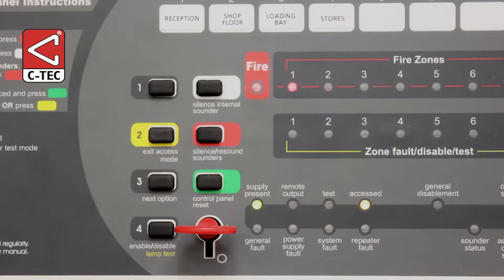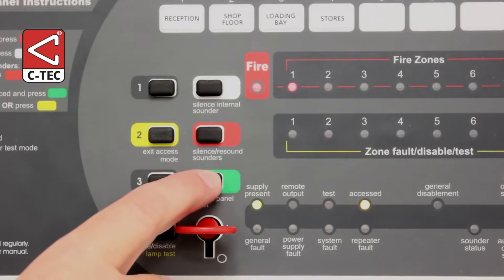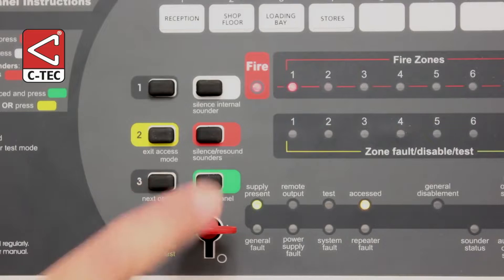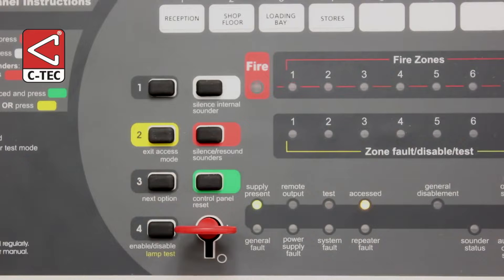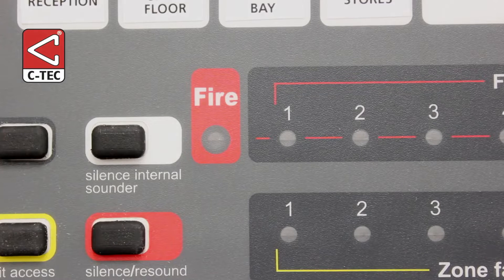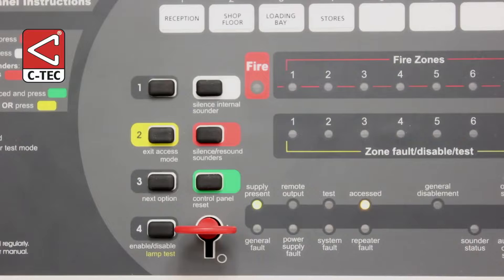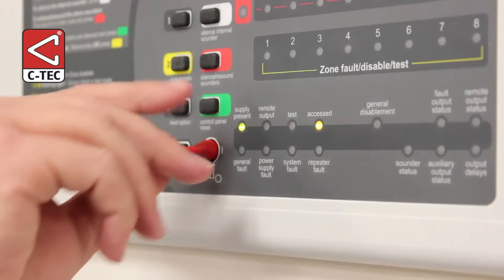After the cause of the alarm has been investigated and you are confident that everything is back to normal, you can reset the panel by pressing the reset button. The panel will give a double beep to confirm that the reset process has started, and after a few seconds its red general fire and relevant zonal indicators will go out. You can now exit Access Level 2 by turning the key to the O position and removing it.